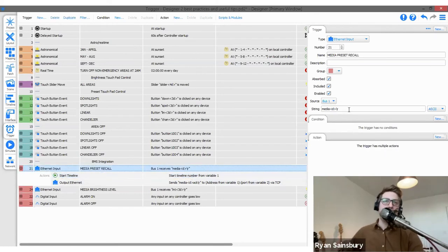You will notice that I've got a \r afterwards. That's a terminating character. That basically clears the controller's buffer. It's really important that you do that when you're using string captures, because you need to have an endpoint and a start point so that you can strip the relevant information.